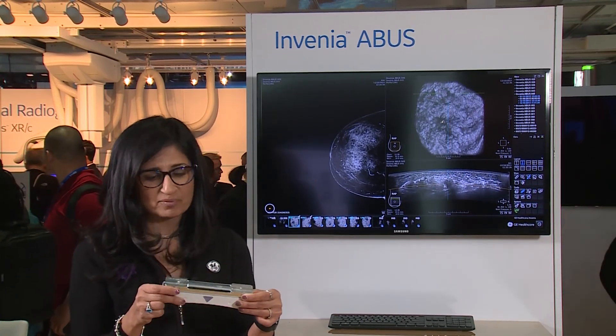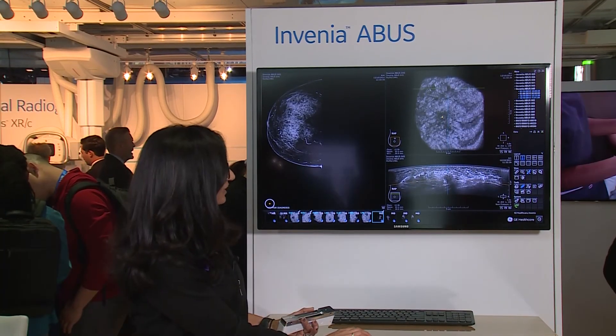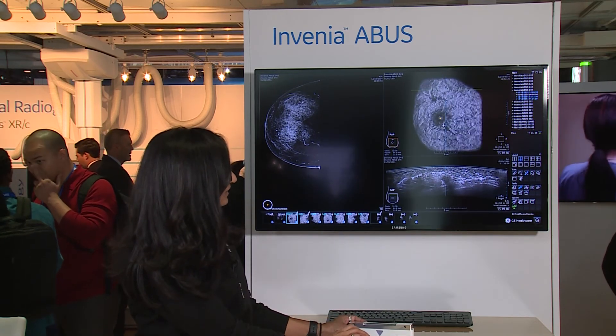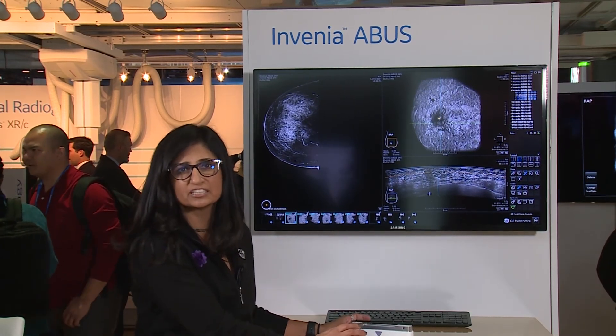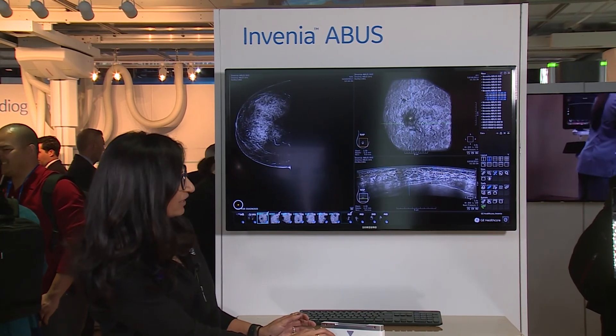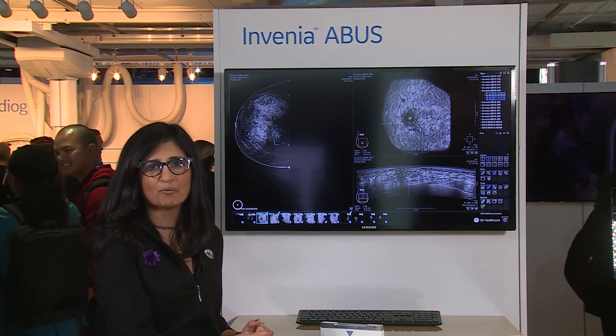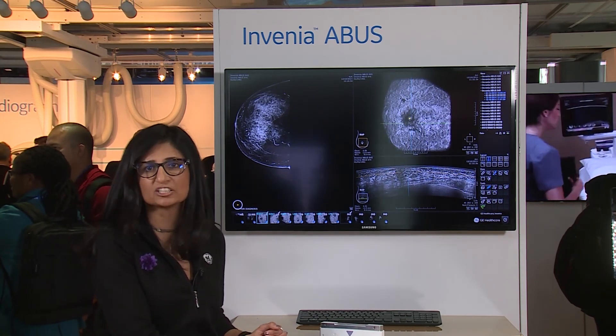The reverse curve probe helps us get really good image quality because we can address the curvature of the breast and get good contact with all of the breast tissue from one end to the other. Once the images are acquired, they're stacked. Our image quality behind the nipple is because of the imaging algorithms and software beamforming we're doing. It helps us see beautifully from one end to the other and from anterior to posterior in every single view, making screening easy for the radiologist to read.